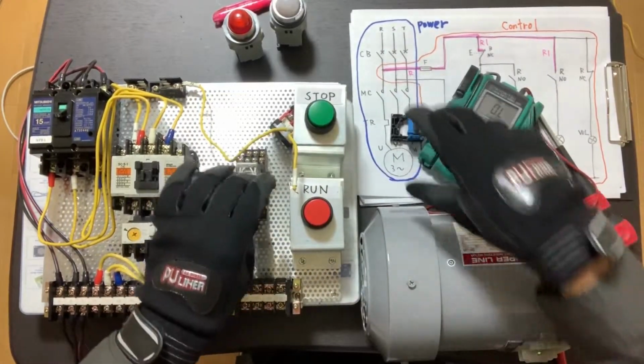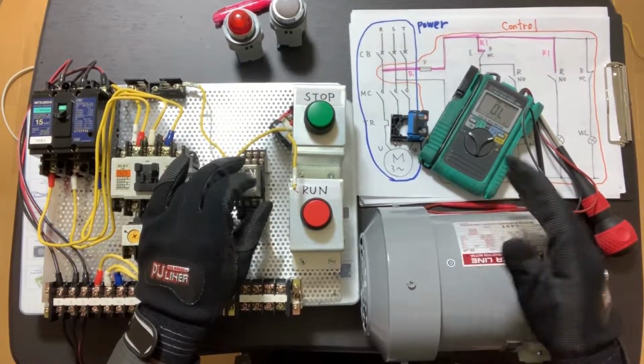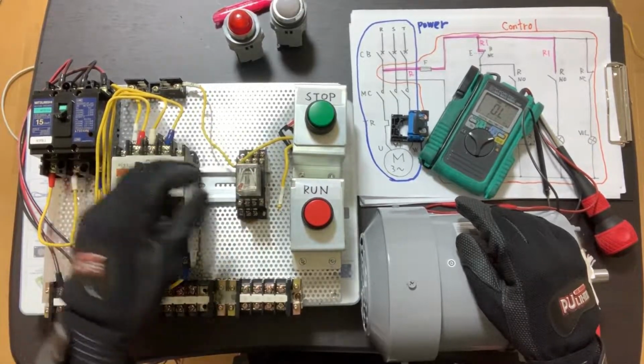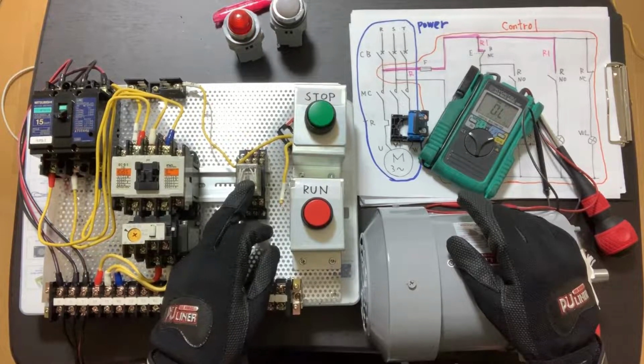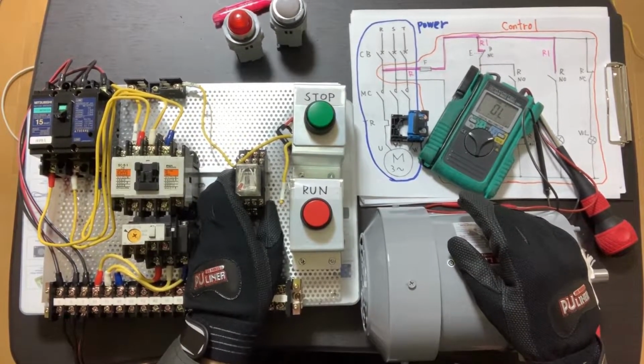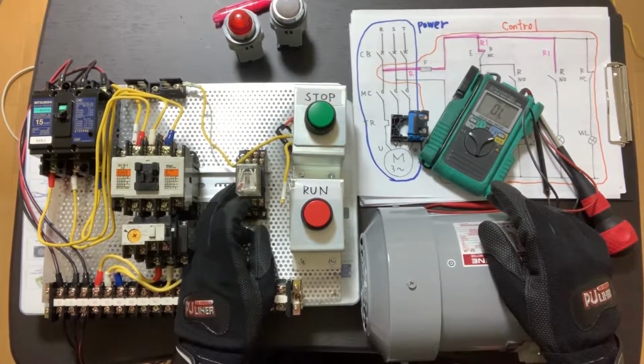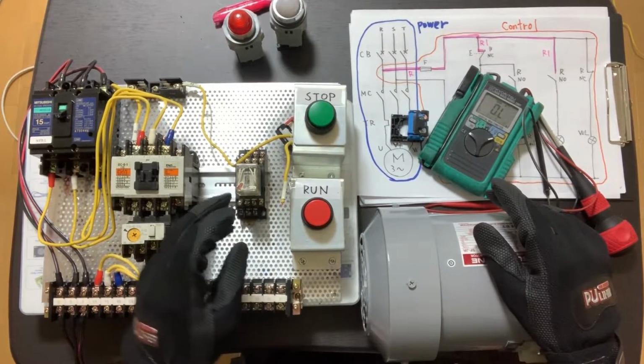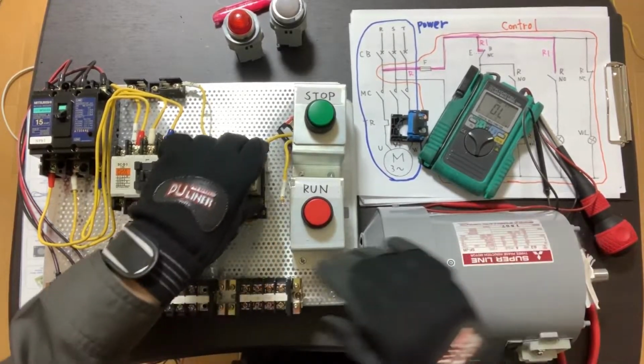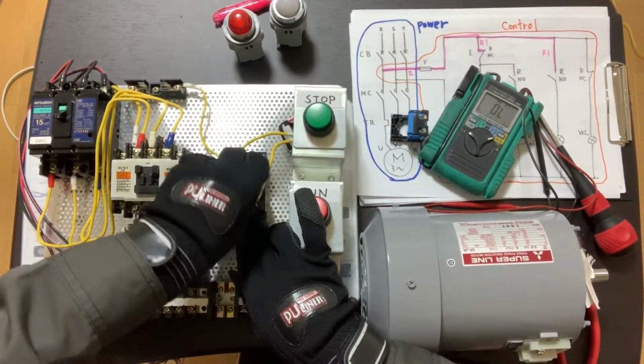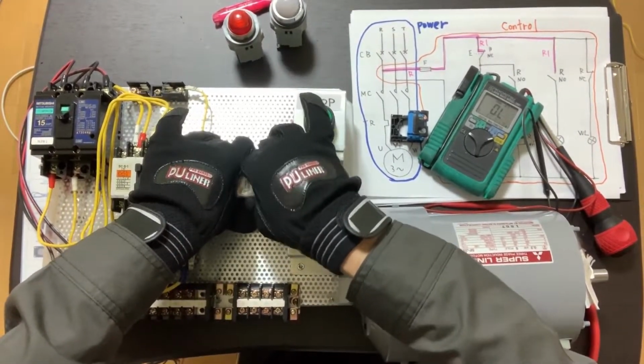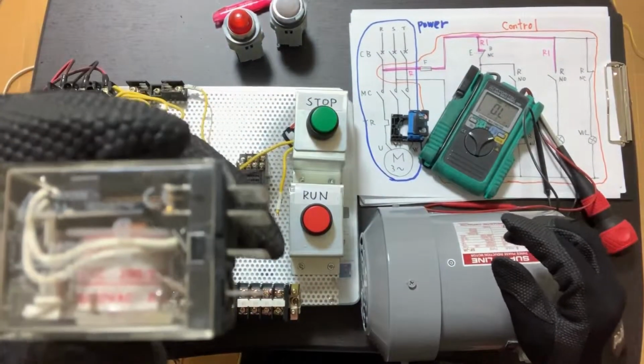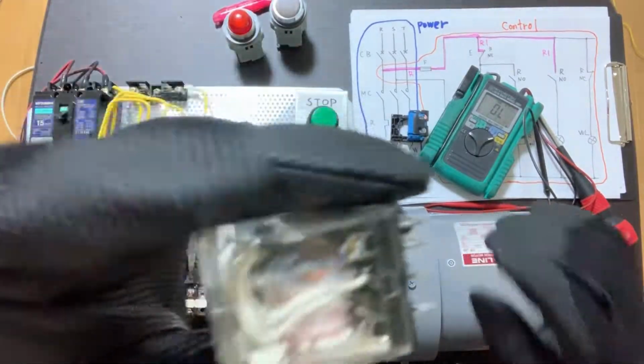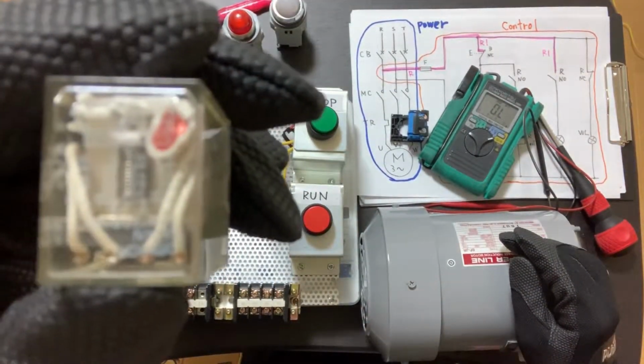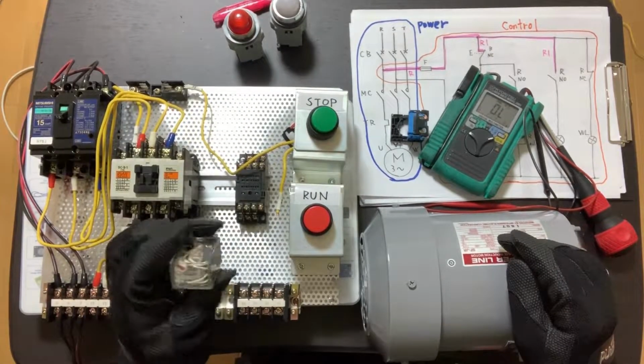But with the relay, you can't check the operating state without a power supply, so it can't be operated manually. The only way to check the excitation condition is by applying the actual voltage to the coil. But the detailed specification, including contact state, is drawn on the body of the relay. I think it's too small for the camera. Sorry. You can check it for reference.